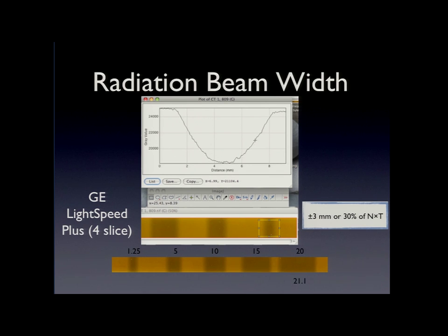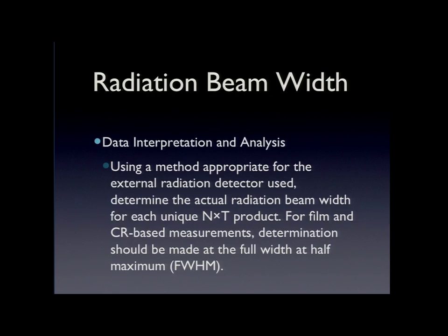So what you can see here is that these are the different measurements that we got. And you can see that we have a problem down here, and that's relatively common on this scanner, that these are off, and unfortunately there's sometimes not much they can really do about it. They do try to recalibrate them, but we really find that on this scanner it's off. But you just need to realize that if they're using this, that's going to affect the dose to the patient. And so that can be something that can be applied during dose calculations.